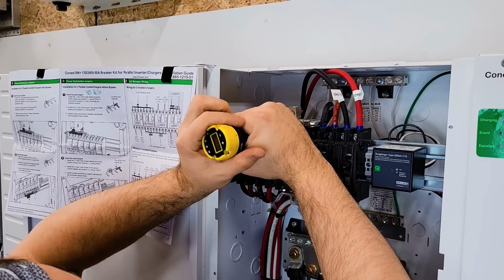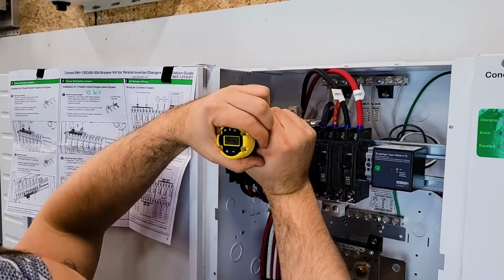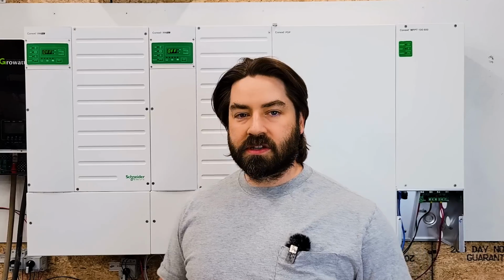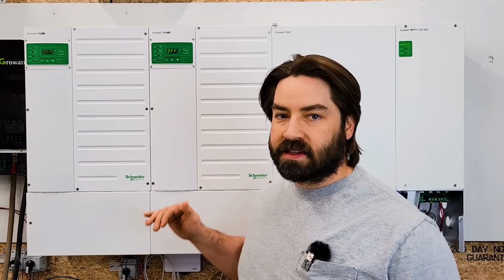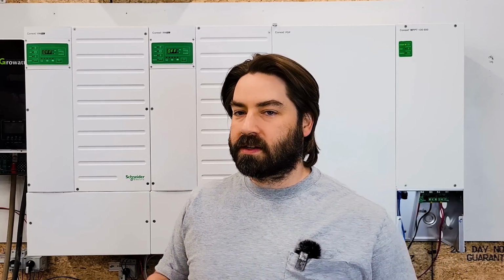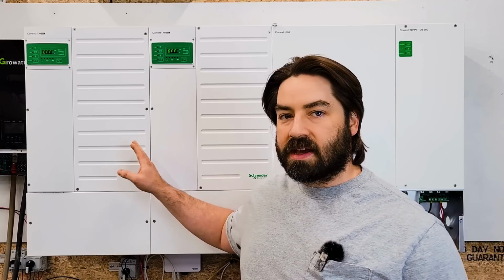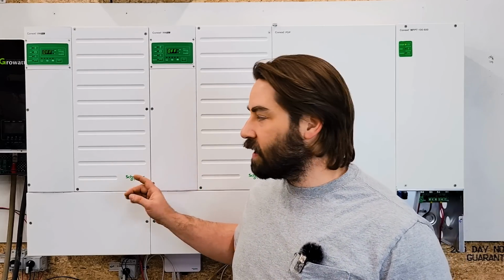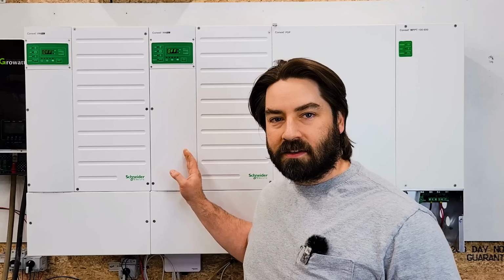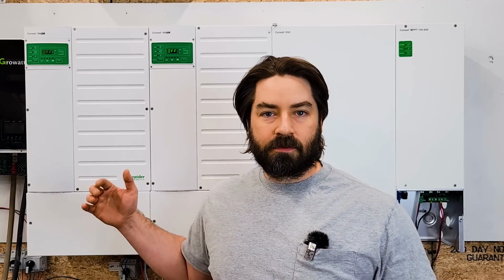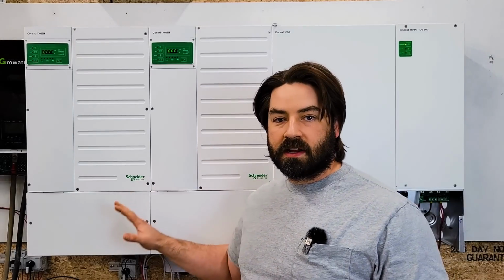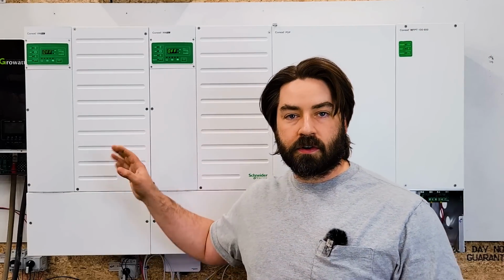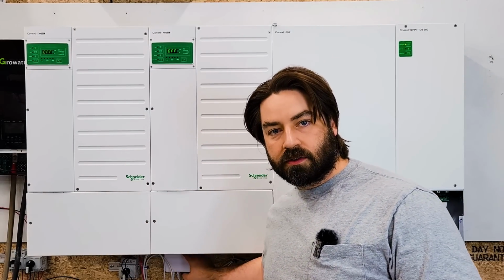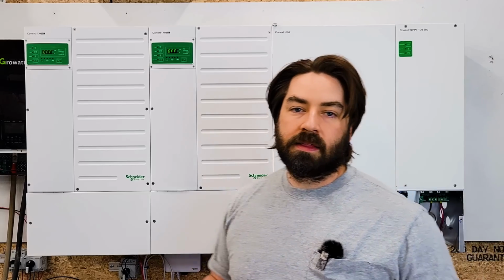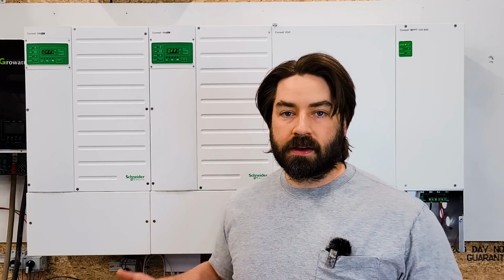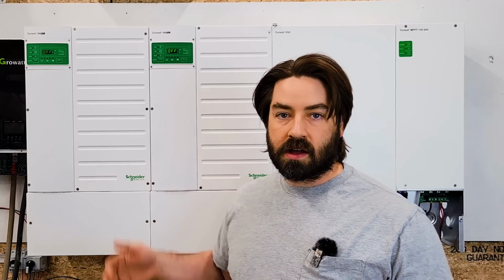Then I went through and zip tied everything in place, and I ran my Cat 5 communication wires. I actually ran all my communication wires at this step, which I probably should have waited on. I'll get to that in a sec. There's a Xanbus communication network, and when you parallel inverters, there's another Cat 5 cable for syncing them up. So I ran all my data communication cables. They connect up the inverters, the charge controller, and they go down to this device called the Insight Home. The Insight Home gives you your Wi-Fi. It allows you to change all the settings on the inverters.